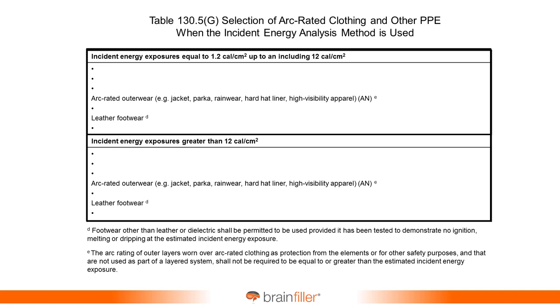Where we have that is right here. This is for the incident energy analysis, 130.5G, and there's a whole lot more than what I'm showing right here. But this table is broken up into the PPE up through 12 calorie per square centimeter, and then at the bottom, greater than 12 calorie.